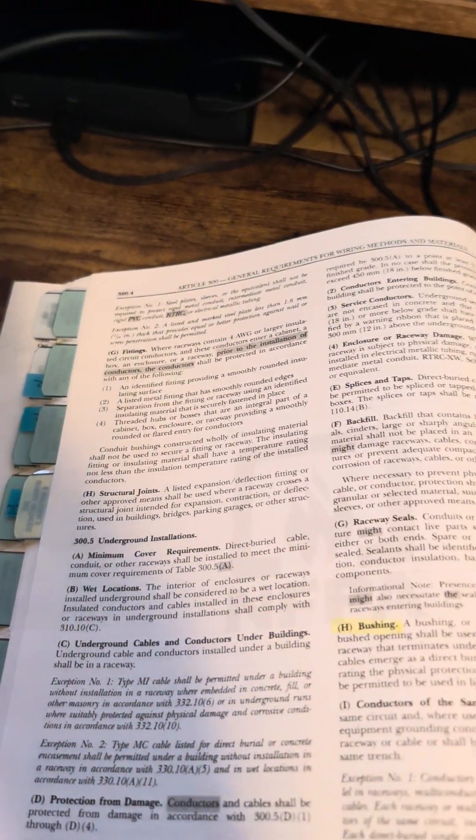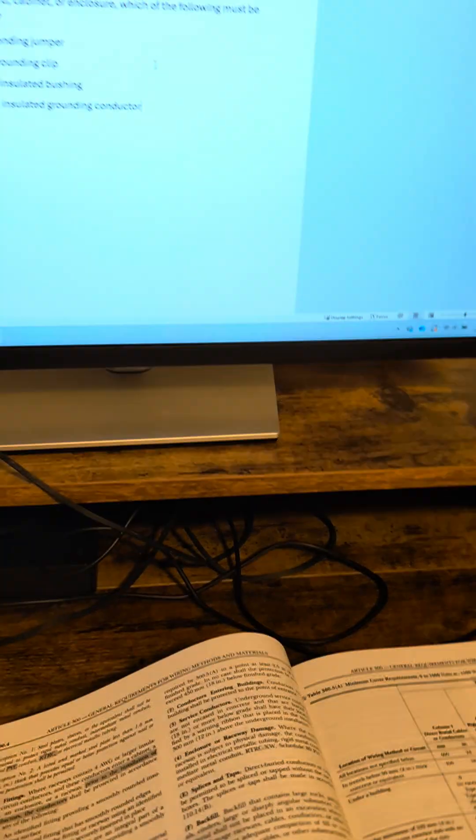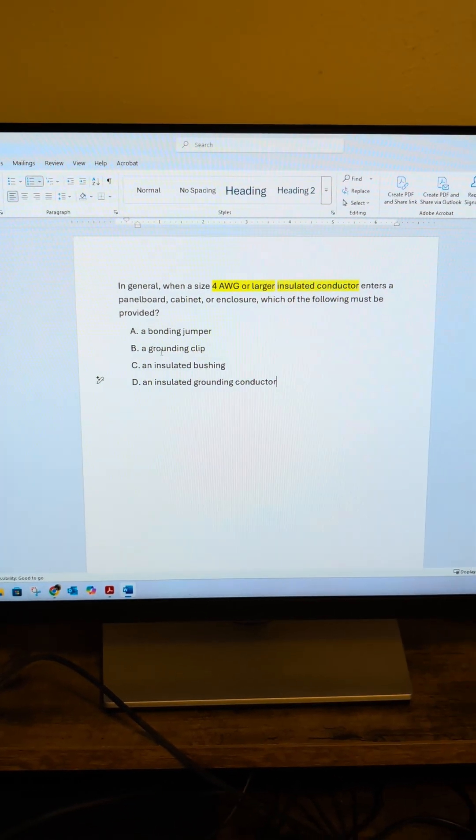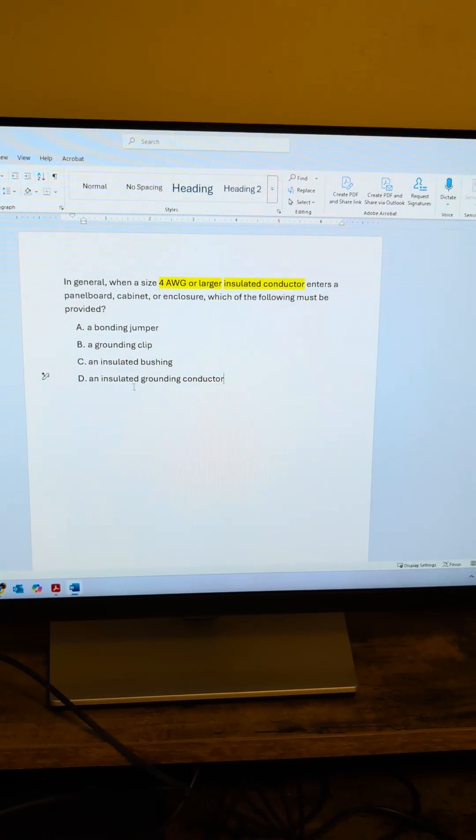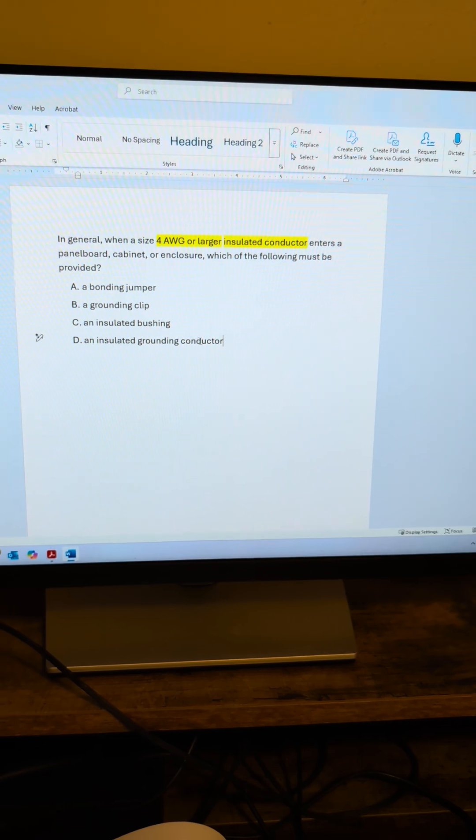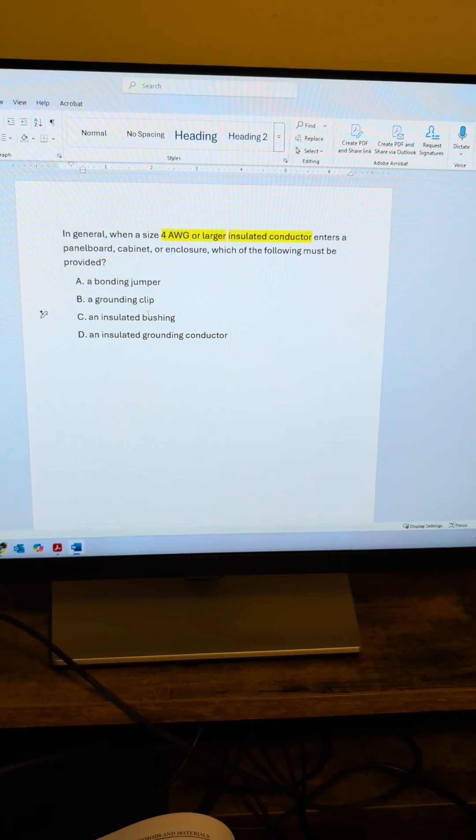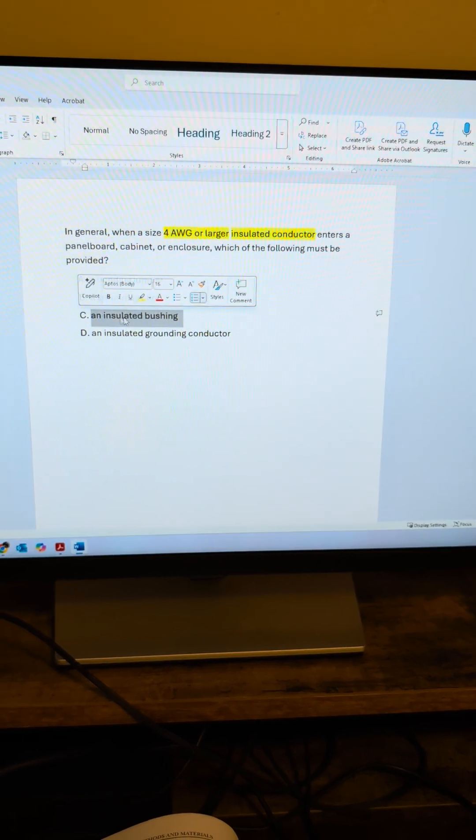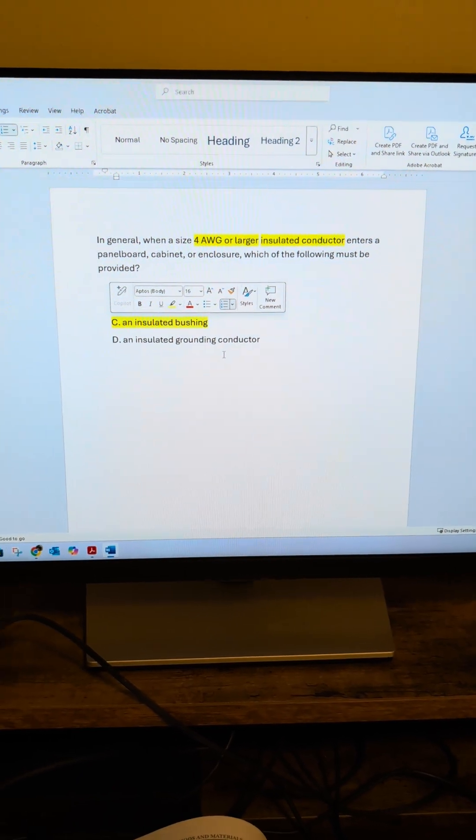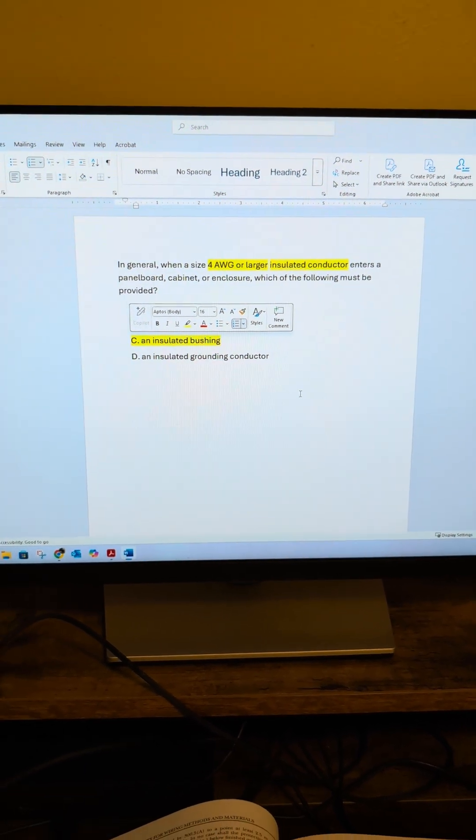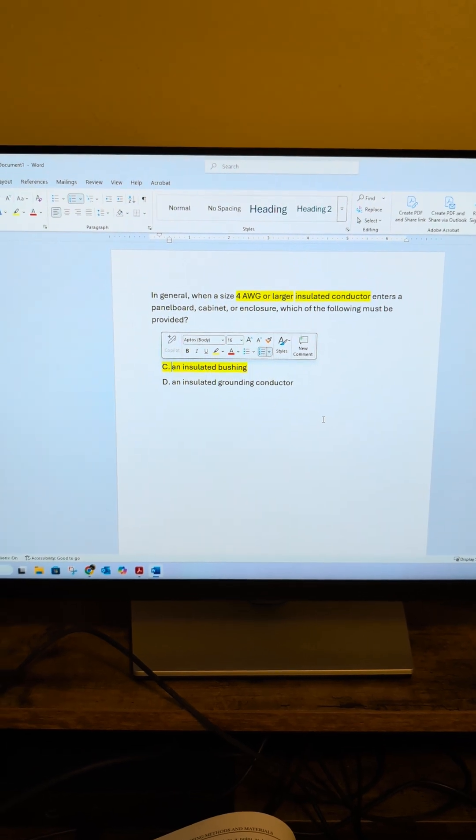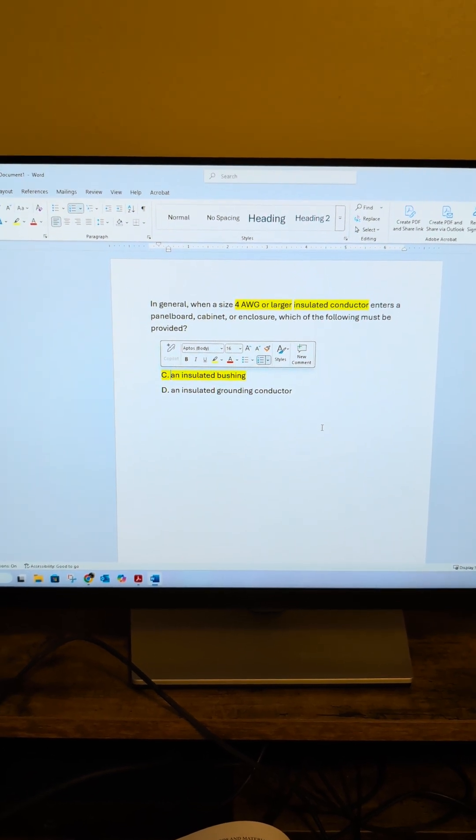All right, so all that to say it's not asking for a bonding jumper or grounding clip or a grounding conductor. It's asking for some sort of insulated bushing. There you go, hope that helps. Don't forget to like, comment, and subscribe.